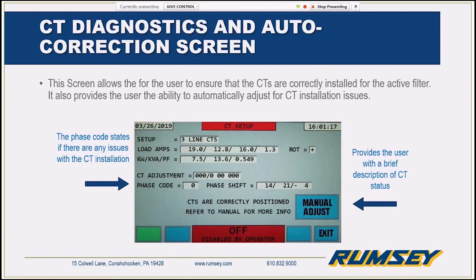the system tells you how it's set up. If it's set up for 3 CTs on the line side of the filter, it'll tell the customer if they've done it correctly or incorrectly. If it's incorrect, there'll be a different number here, a brief description. With that number in the manual, it gives a very specific way to physically change the wires or change the CTs to meet the error. Or with most options of error, a green button appears here that says automatically adjust.